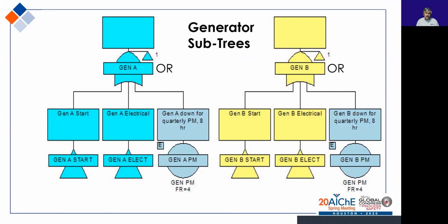Here are the subtrees for the generators themselves. These are OR gates, so anything that happens underneath will prevent the generator from providing power. The generator must start, and the electrical system must work for the generator. And we already know that the generator is going to go down once a quarter for 8 hours for the preventive maintenance. FR is the frequency rate for the preventive maintenance, 4 times per year. Gen A and Gen B have similar subtrees.